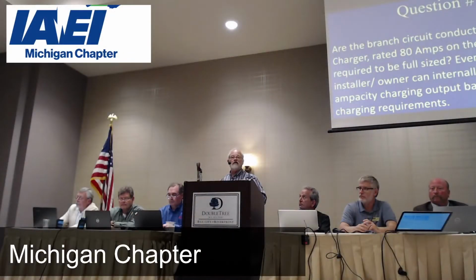And then restricted access shall prevent the user from gaining access to the adjusted means, and then it gives you 3 conditions that have to be met with that. But nonetheless, the 2020 edition NEC would permit that, utilizing the lesser ampacity when you could adjust that equipment down, provided it meets the restricted access. Okay. Any questions on that? No?